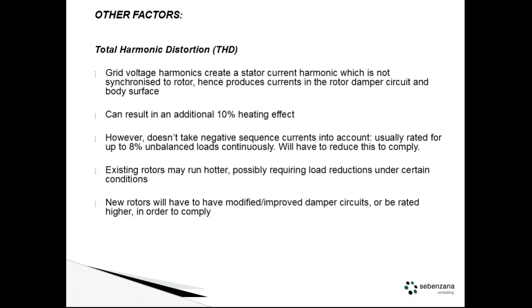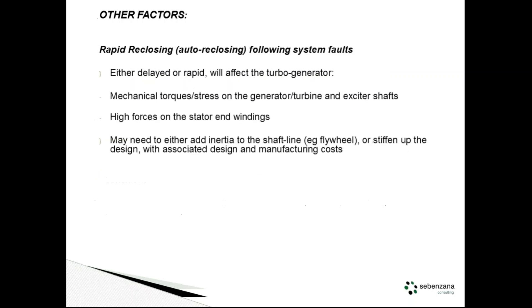Rapid re-closing of breakers onto faults — whether delayed or rapid — causes mechanical torque stresses on the shaft and higher forces on the end windings. To cope with that, if you want the machine to handle it, you have to build in more inertia — possibly a flywheel — and stiffen up the design. Again, costs.